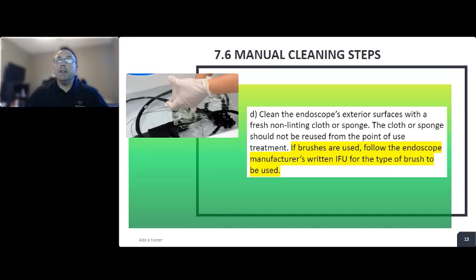But again, driving into understanding the manufacturer's IFUs. In the manual cleaning steps, it tells us if brushes are used, I love that statement, if brushes are used, follow the endoscope manufacturer's written IFU for the type of brush to be used. That's good. But the problem I'm going to show you in a few minutes is, do the manufacturers know what type of brush to properly use? Have they done any research? Is there anything out there on that from a third party or from the brush manufacturers? Again, this is pretty vague. It's just throwing it all back on the manufacturers.